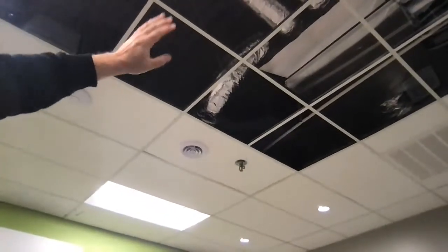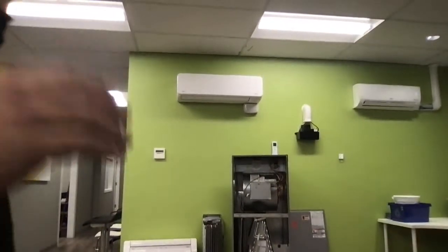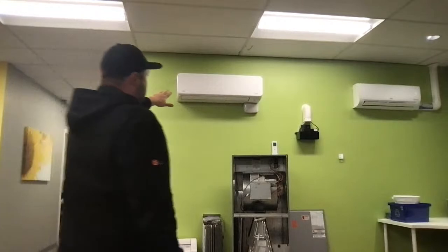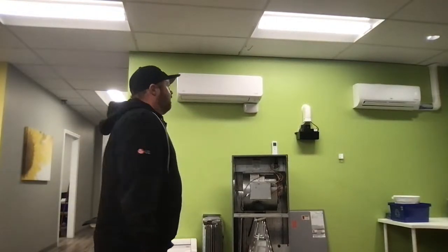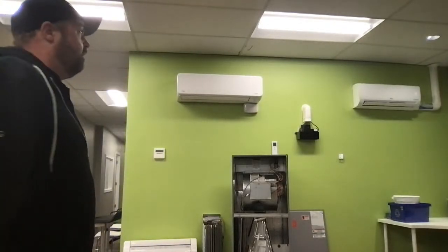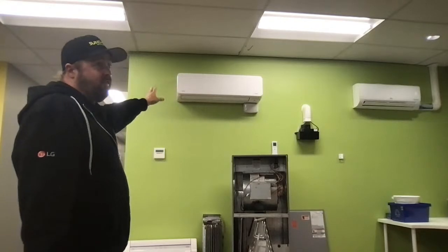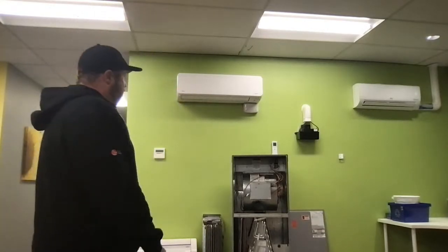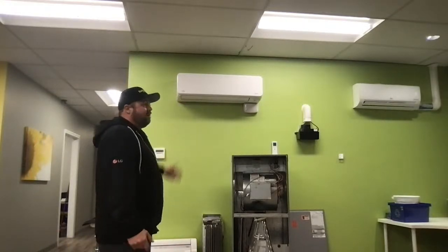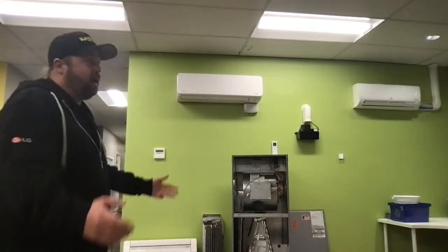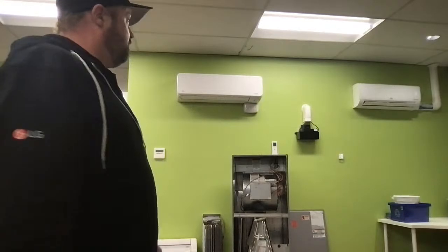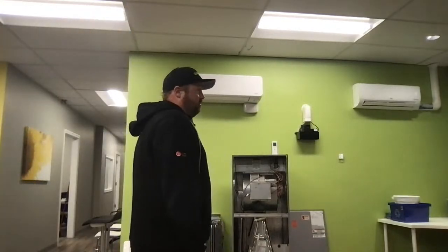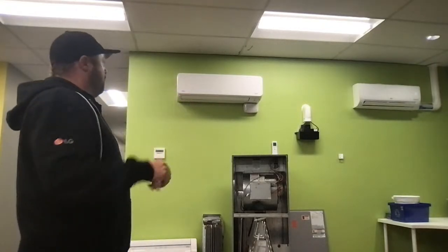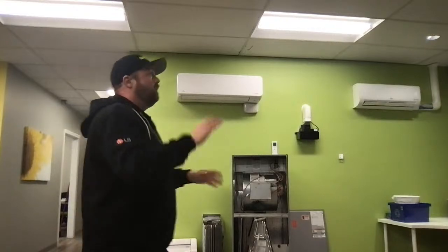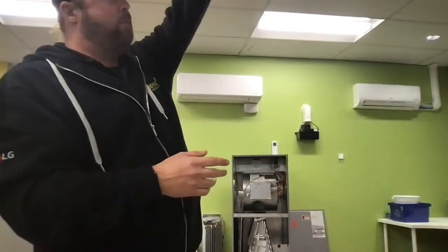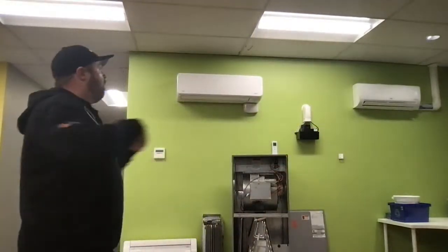The reason that we really push these a lot harder now is because, especially 2 stories, we've put in a bedroom, again, spending a lot of money to get 1 bedroom, right? 100% of the time it's oversized. Nobody's bedroom is big enough, really, unless it's a really big house, to accommodate a 7,000 BTU. I think 6,000 BTU is the lowest that I've really heard of indoor heads. But bedrooms, they need 2, 1.5, maybe 3,000 BTUs. So when you're starting off at 6 or 7, you're at least double the size. They come on, they shut off. They come on, they shut off. They don't really produce the amount that they would. Whereas if you have it on the main floor, if you have something that's properly sized for the space that you're looking to get, it runs all of the time.